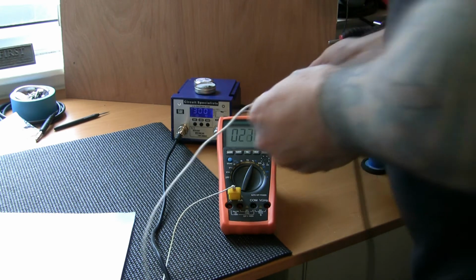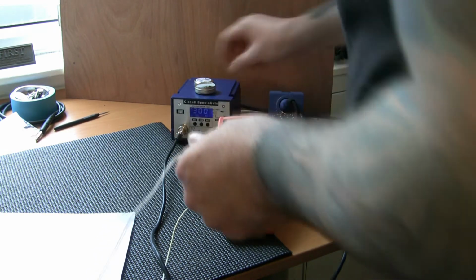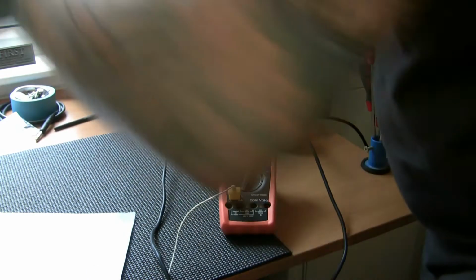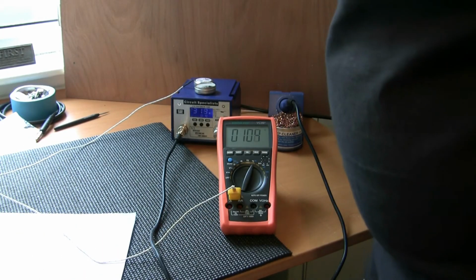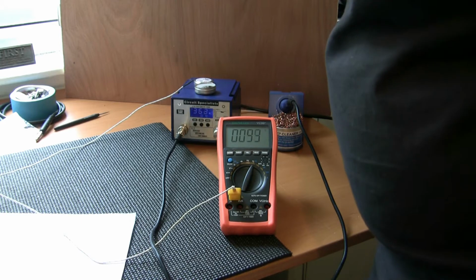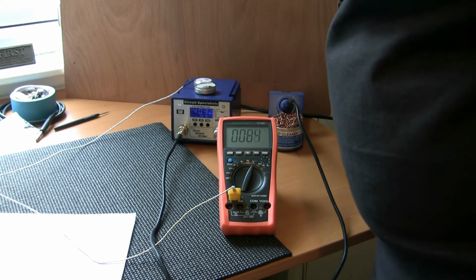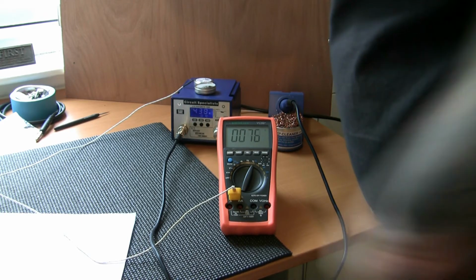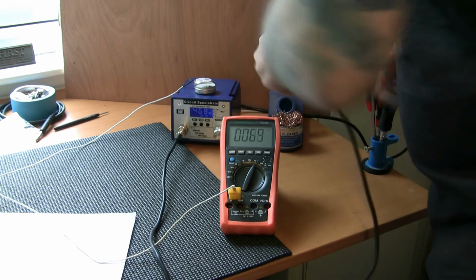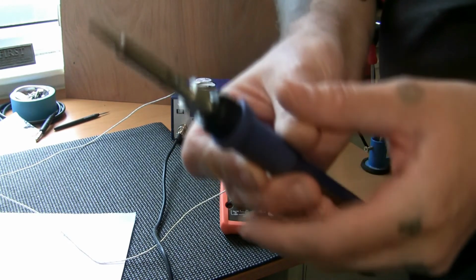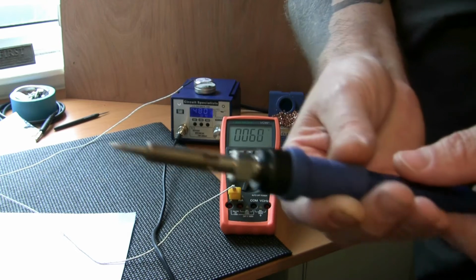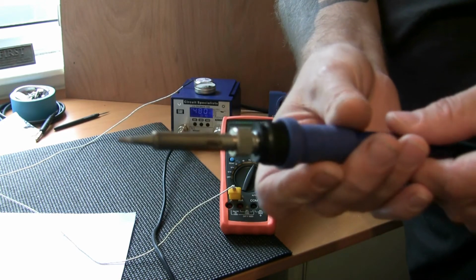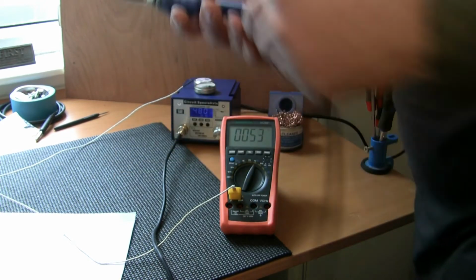So what we're going to do is clean that tip and now bring it up to 480 degrees. And I'm going to read the rest of this email. If you're using a wide chisel tip, please confirm how old this tip is, or if it's a new tip. Are there any signs of oxidisation or corrosion of the tip? If so, this can be removed with light emery paper. Would you call that corrosion? I don't think so. It's got a little bit golden, but that's not oxidisation, is it? That's pretty good. It's a fine tip.